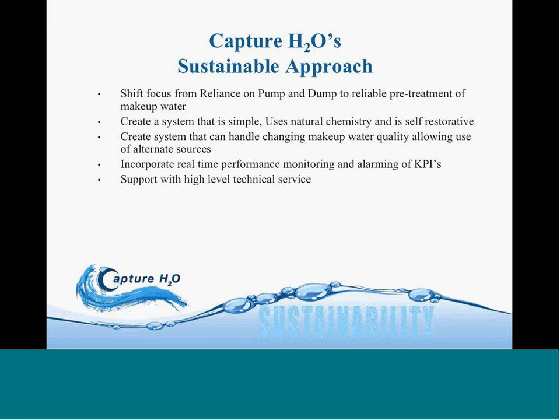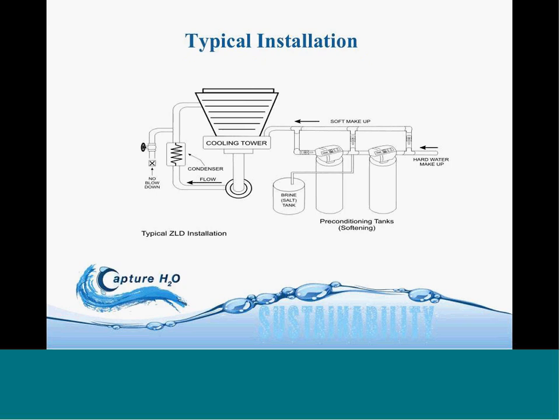So what does Capture H2O do? We shift the focus of the water treatment from the reliance on that blowdown control, where you have to dump water and pump chemicals back in, to relying on a pretreatment system to treat the water going into the cooling system. We create a system that's simple and uses natural chemistry and is self-restorative, meaning it will remove existing deposits, and it's very forgiving. This system also allows us to handle varying amounts of different water sources going to the system without having to make adjustments. We incorporate real-time performance monitoring and alarming of the key performance indicators. And finally, we support the system with a high level of technical service.